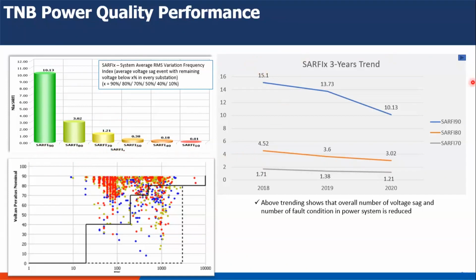In terms of trending, we can see that over the last 3 years, from 2018 to 2020, the SARFI has dropped quite significantly, especially SARFI 90. From 2018 it is 15.1%, 2019 is 13.73%, and 2020 is 10.13%. Same goes for SARFI 80 and 70. It has dropped from 4.52 in 2018 to 3.6 in 2019 and 3.02 in 2020. SARFI 70 also dropped, from 1.71 to 1.38 and 1.21. So we can see a big drop over the last 3 years from 2018.